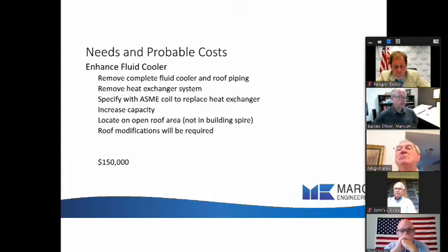The very first thing I would do is enhance our fluid cooler. I would recommend removing the entire system. The roof piping has been problematic. The fluid cooler that's in the spire, I would remove, along with the heat exchanger and the pump in the room below it. I would specify a different fluid cooler that has an ASME coil to replace the heat exchanger. I would increase the capacity of this unit. I would locate the unit on the roof in the middle of the building. I would not put it in the building spire again. This unit needs to be off by itself and allowed to free draw air. There would be roof modifications required to support this load in the middle of the building.